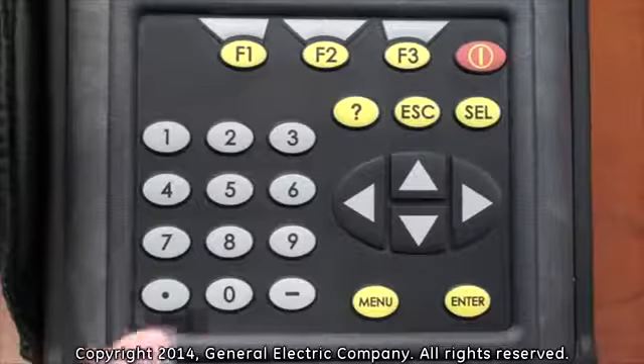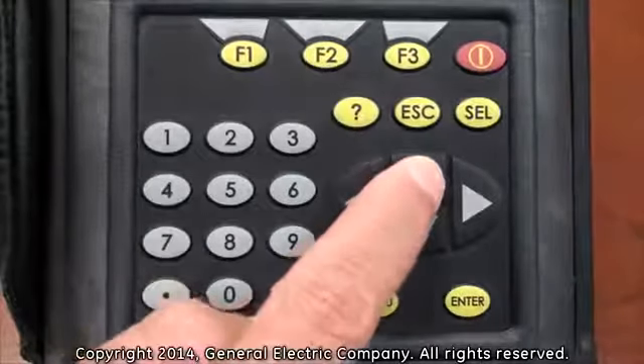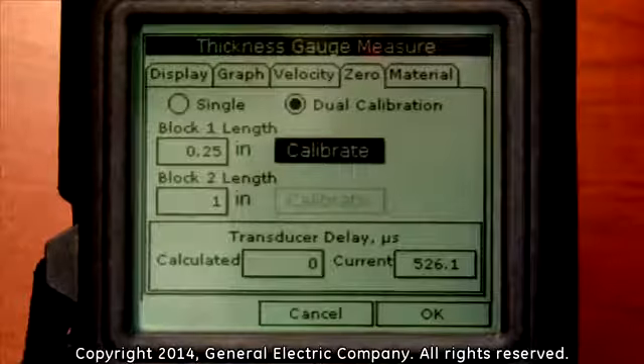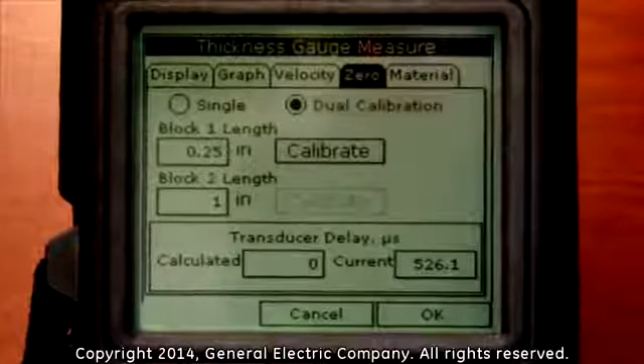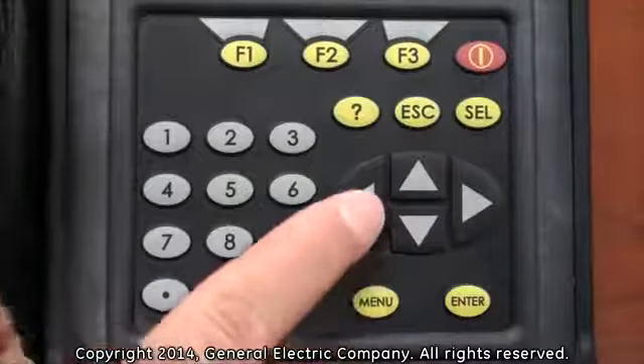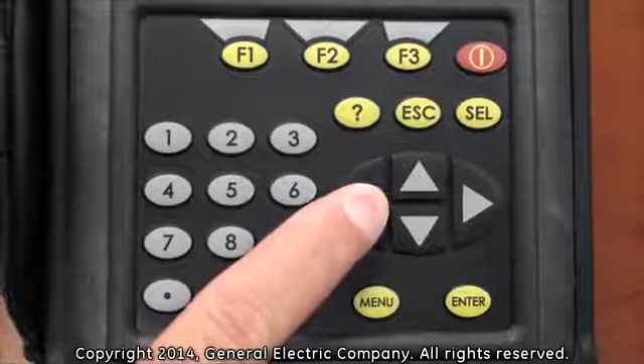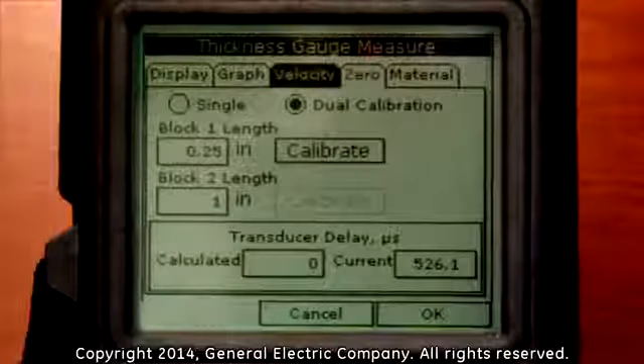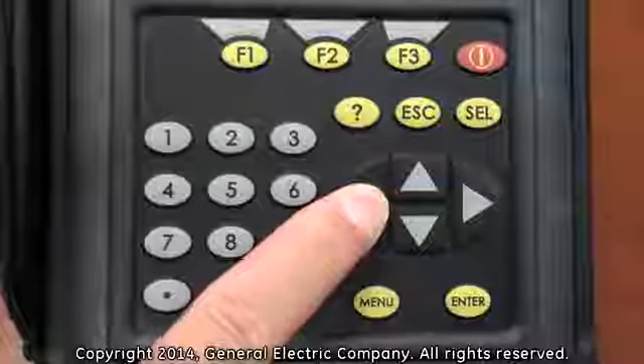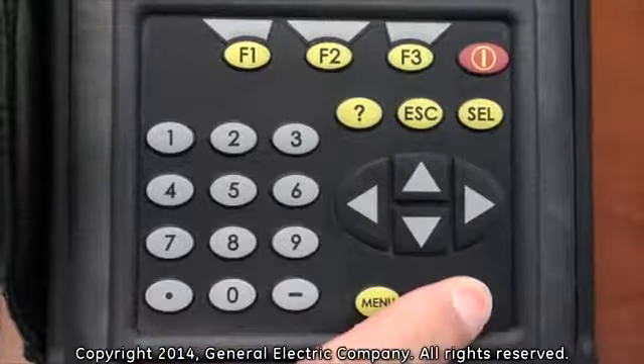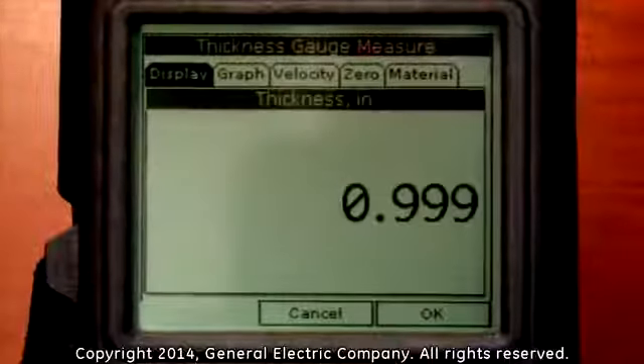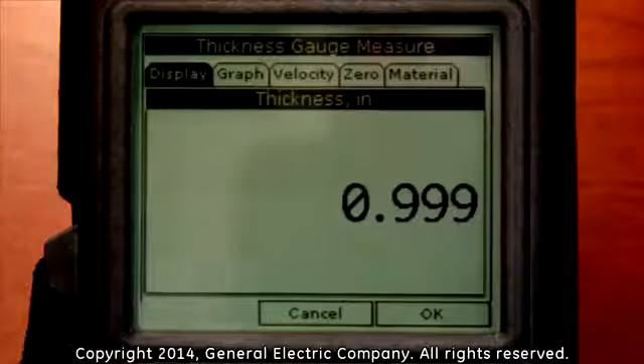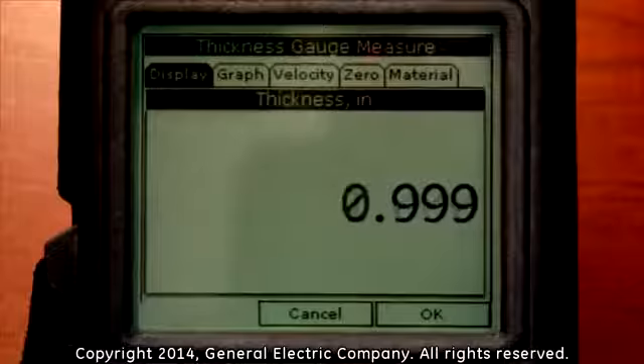To verify the calibration, use the up arrow key on the keypad to navigate up to the Zero tab at the top of the display. Then use the left arrow key to navigate over and highlight the Display tab. With the Display tab highlighted, press the Enter button on the keypad. This will take you to the thickness gauge measurement display.